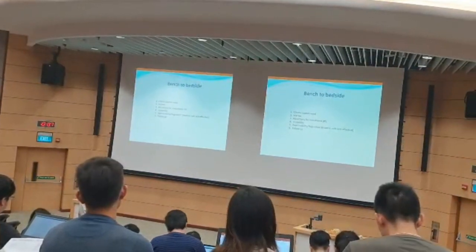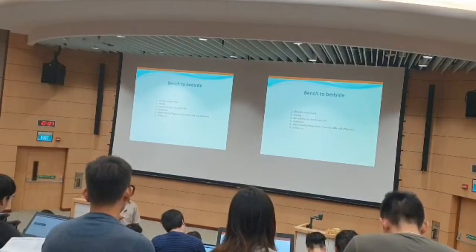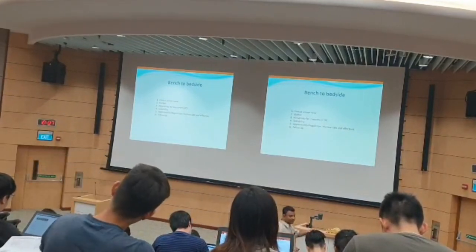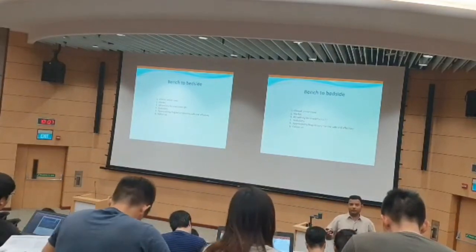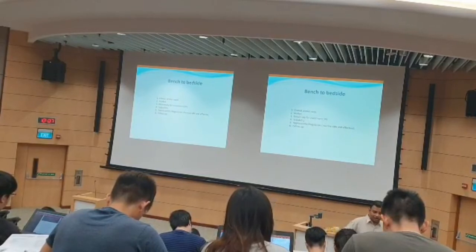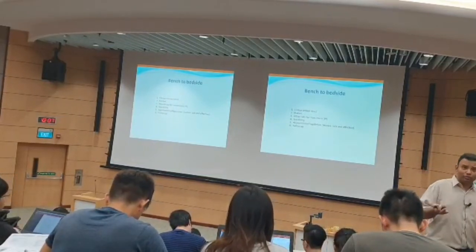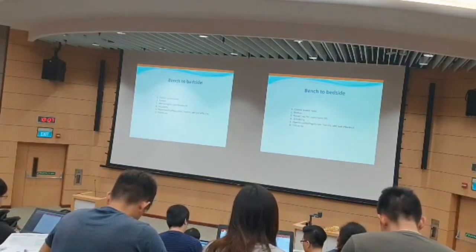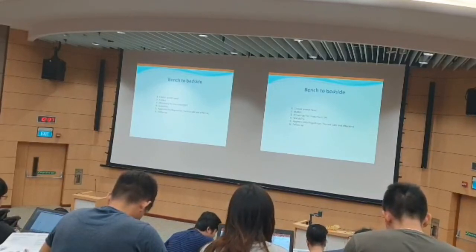The main thing they will look for is the safety, and they will look for the performance or efficacy. The device must be safe, because you put the device or the biomaterials into the patient, it should not kill the patient, right? If there is an immune response, there is a potential that it can kill the patient. So they will ask for evidence: show me the experiments that you have done to ensure that this particular material is safe when it's implanted into the human body.